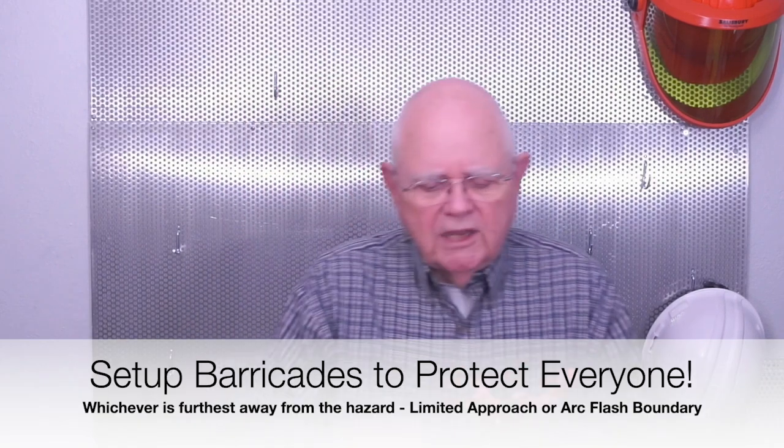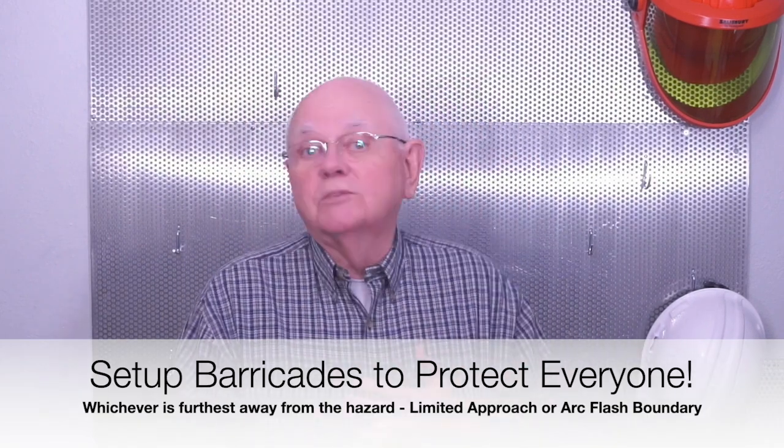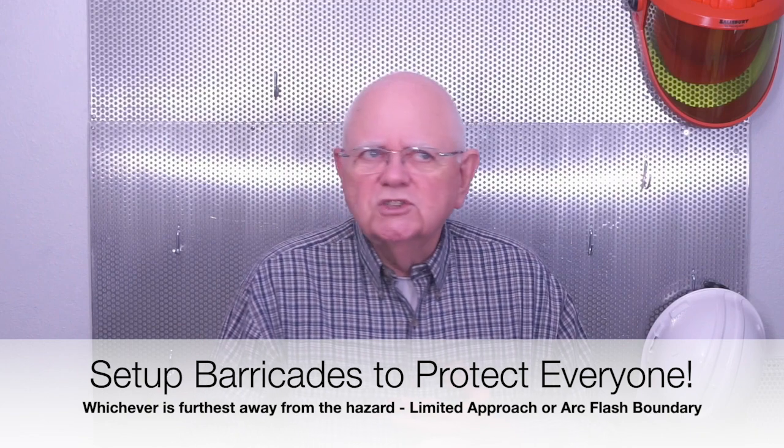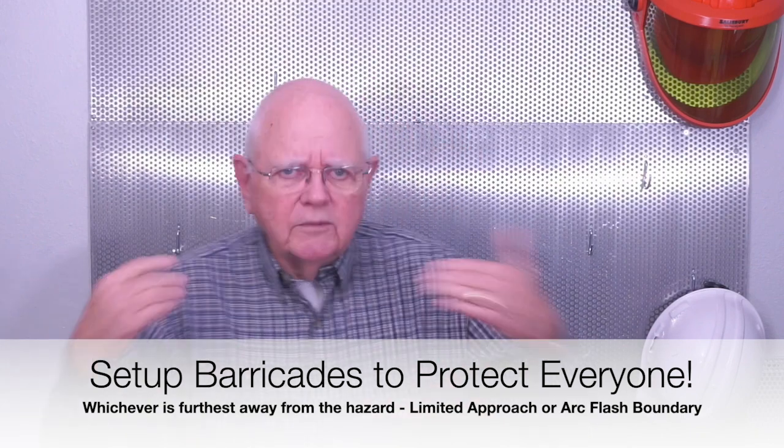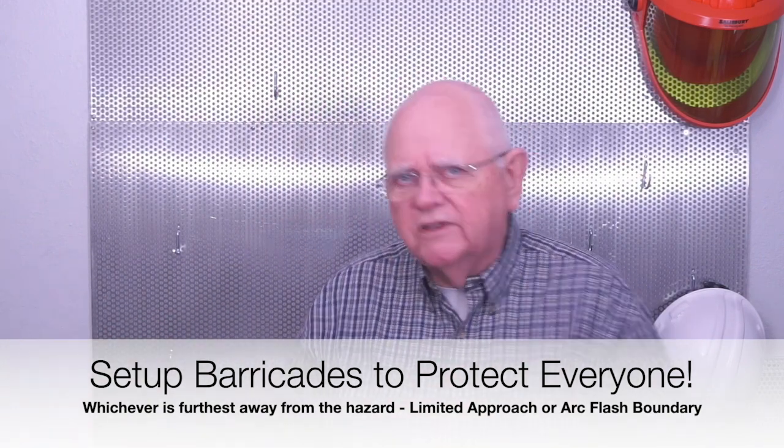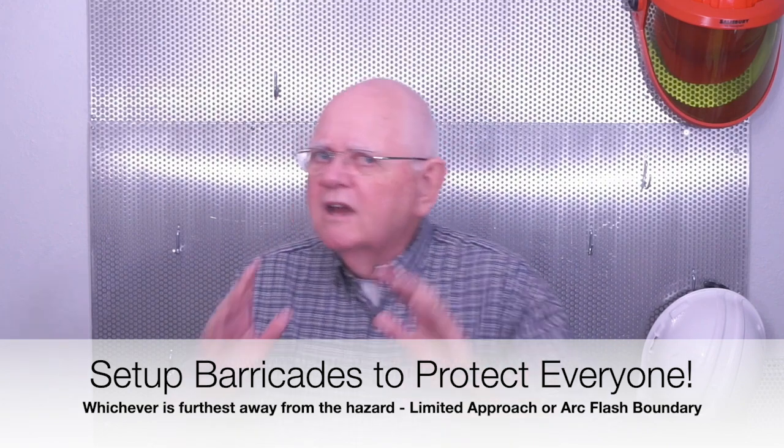Now, another thing we've got to do. We've done our JSA. We've looked at some PPE. We've got to establish some barricades. And on a construction job site, we're going to do that, of course, at the limited approach boundary or the arc flash boundary, whichever is greater. But you've got to protect everybody out there. And on a job site, there can be a lot of stuff going on around you, right? So keep that in mind when you set up your physical barricades.